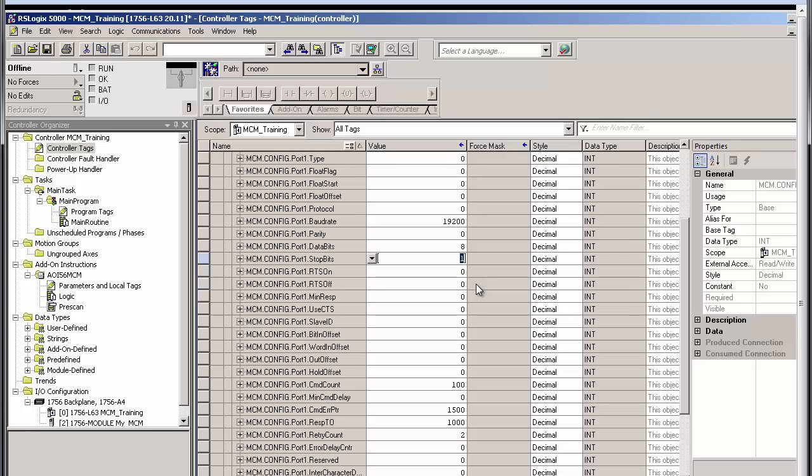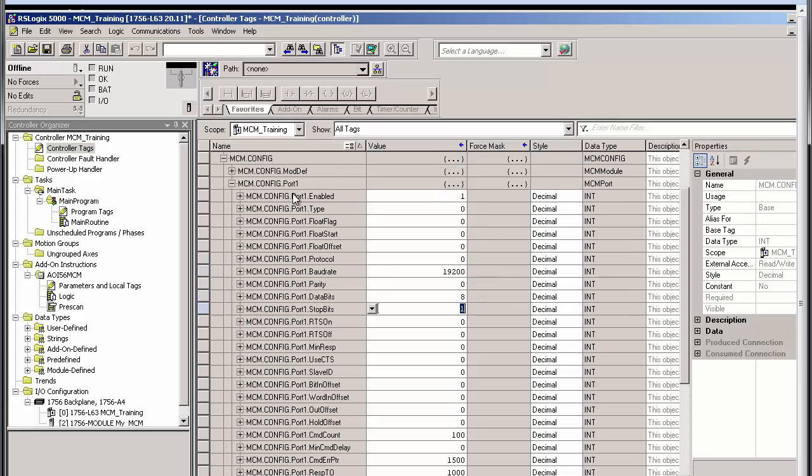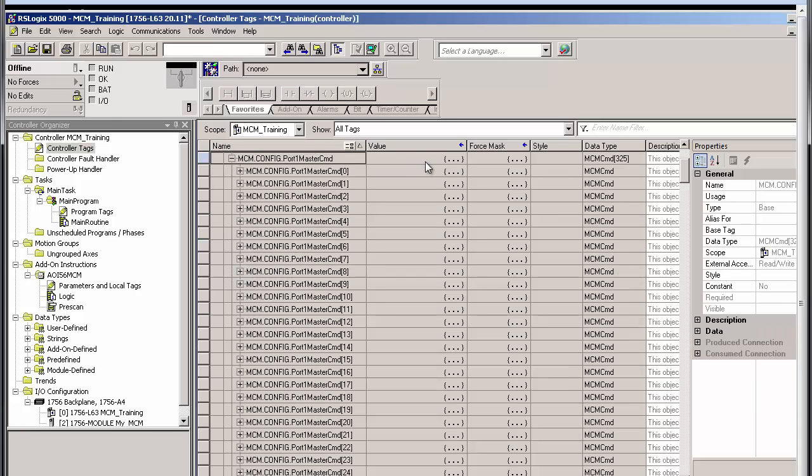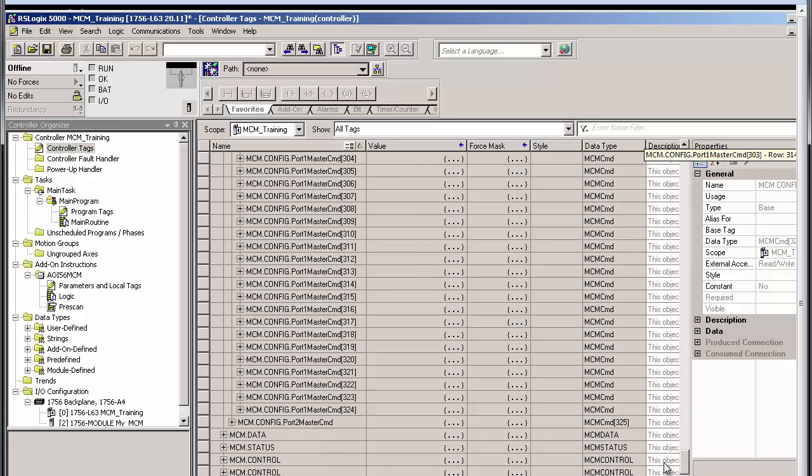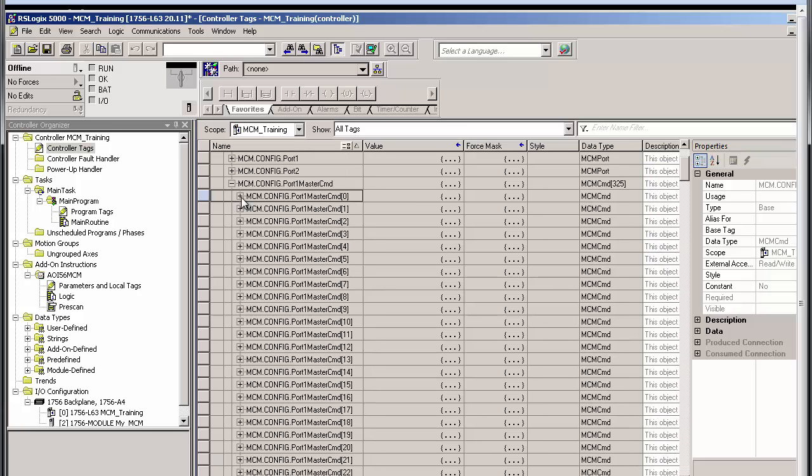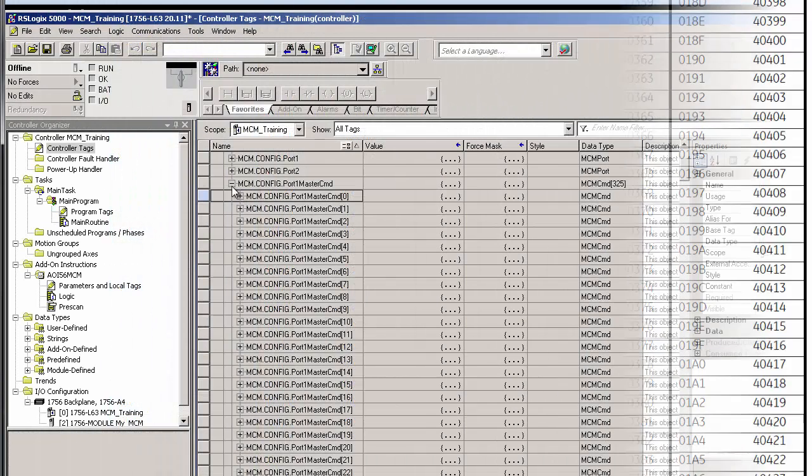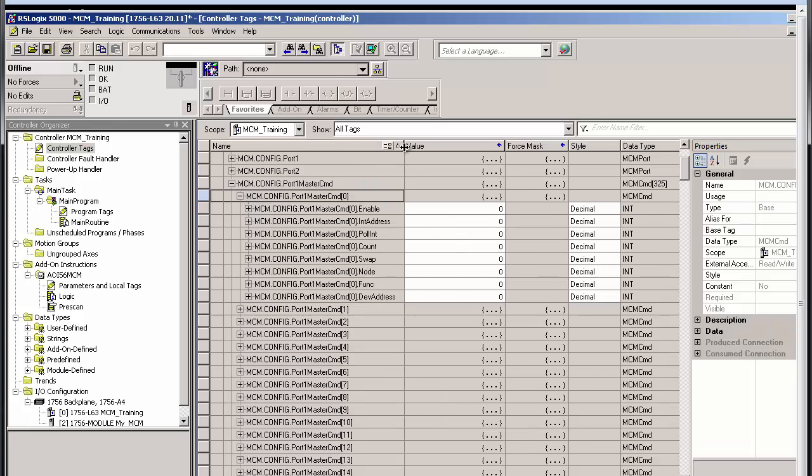Each port on the MVI56E MCM has a master command controller tag for creating master commands. For port1, the tag is at MCM.config.port1 master command. And here we can create up to 325 commands for the port. I'll create a few commands to illustrate how different commands work with our database configuration. Note that you'll need to consult the user manual for your slave device in order to know what addresses in that device you would want to read and write data to. I've done this for my power monitor, so I'll begin by setting up a master command to read the minimum and maximum phase A voltage.